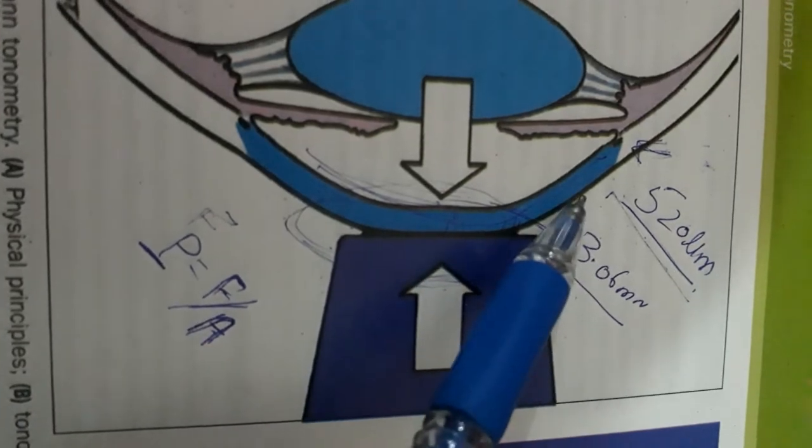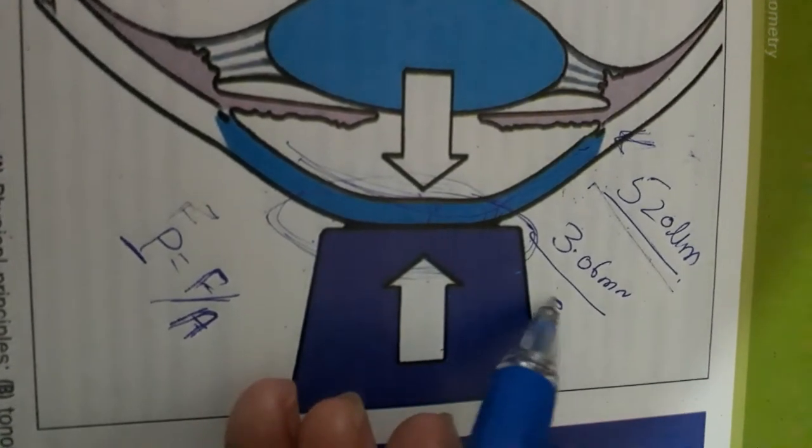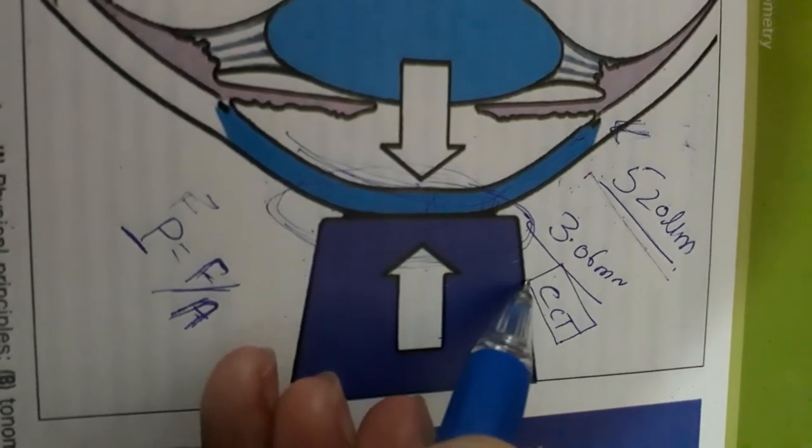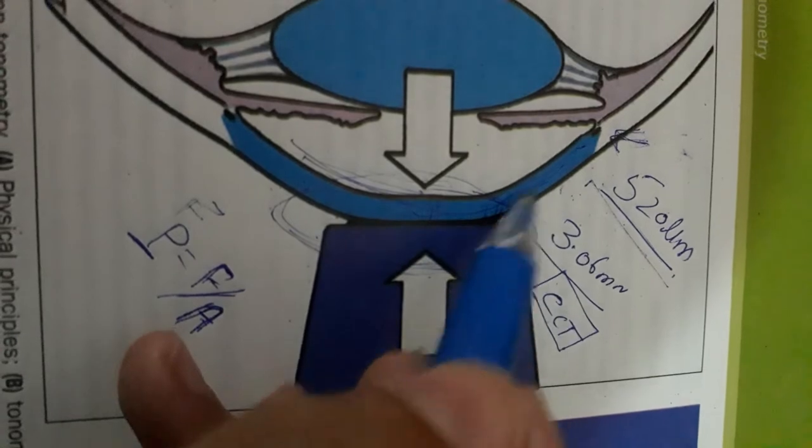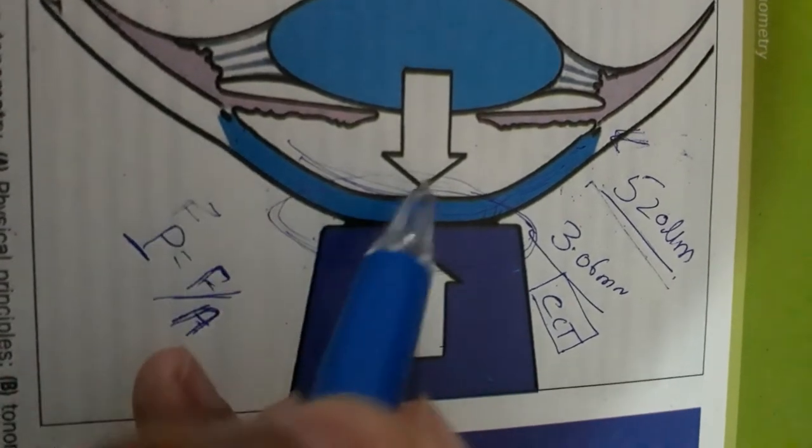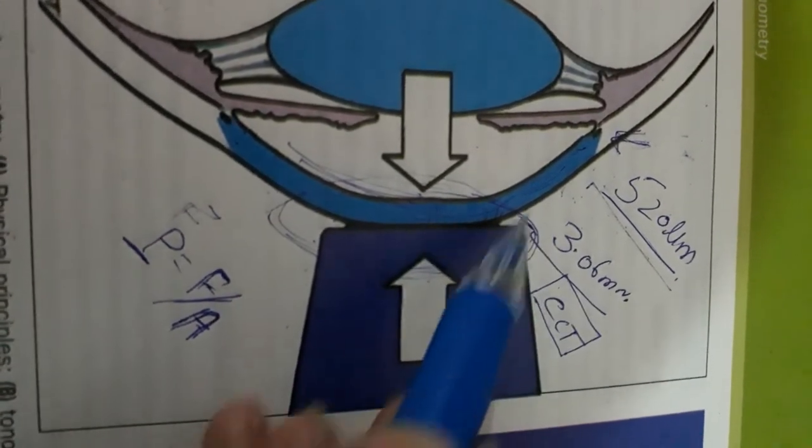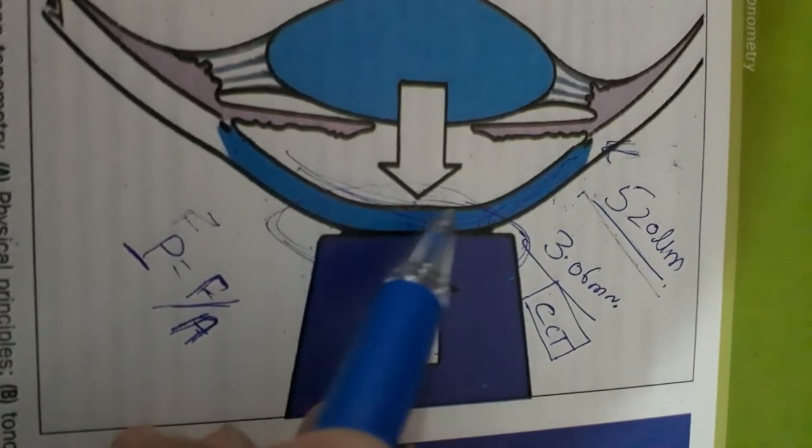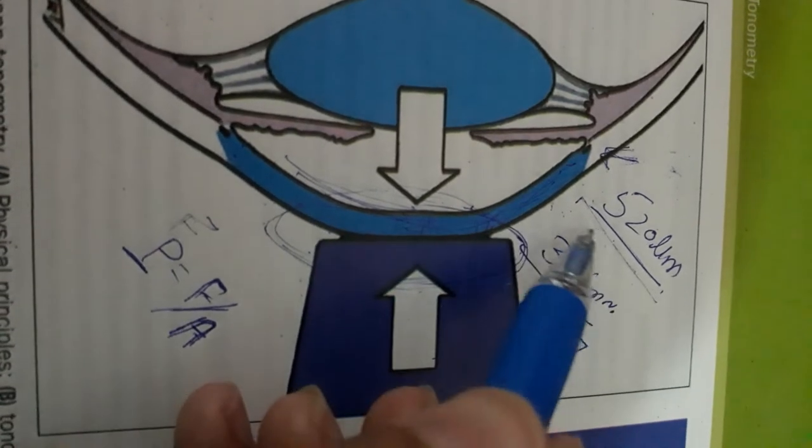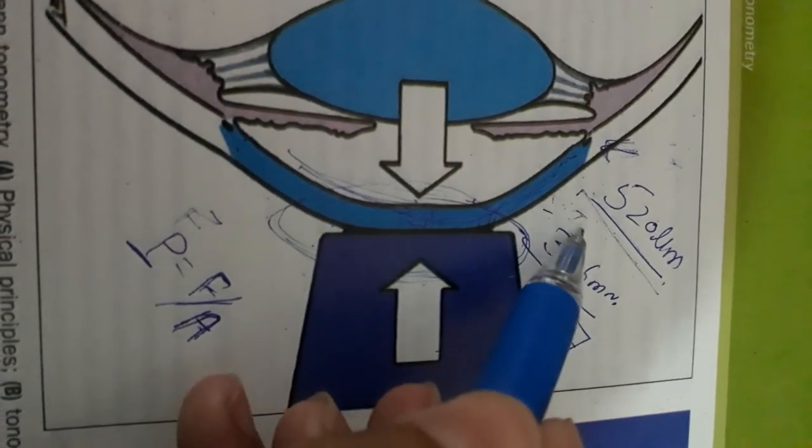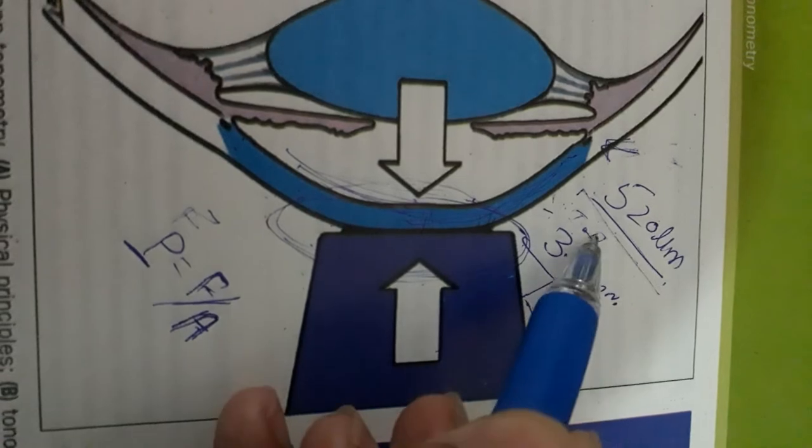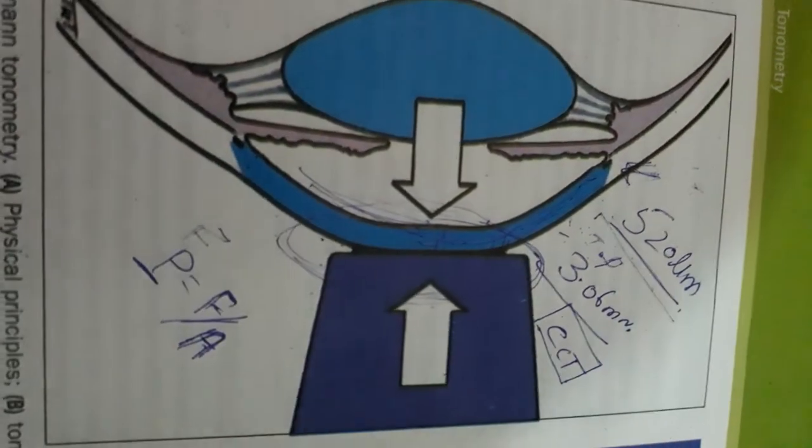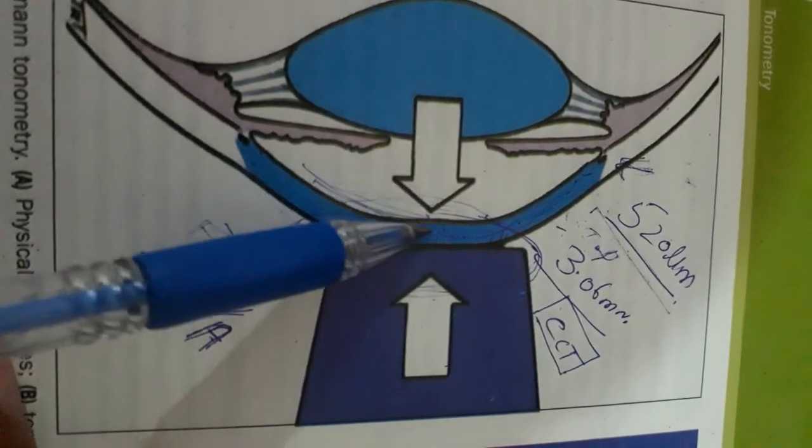The most important thing is central corneal thickness (CCT), because any change in the cornea will change the IOP measurement. If the cornea is thick, there will be overestimation of IOP. If the cornea is thin, there will be underestimation of IOP.